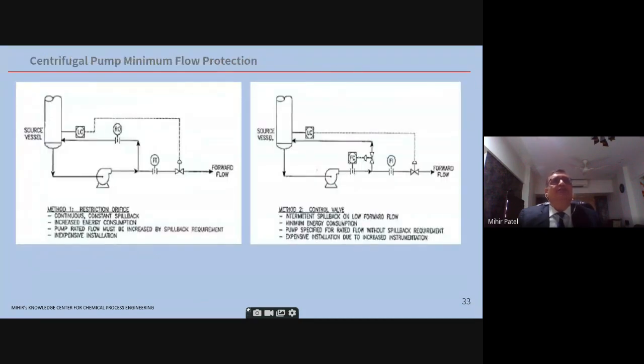Now we come to centrifugal pump minimum flow protection. For a centrifugal pump, to avoid cavitation, there is a minimum safe flow, MCF what is called. It has to be ensured that the flow is always above that. There are two ways you can do it. One is you can have a restriction orifice going back, as you can see in the left-hand figure. The important thing to remember here is that the flow through the RO has to be added to the capacity of the pump. So if you have a 5 meter cube requirement in the process and the minimum flow through the RO is 1 meter cube, the capacity of the pump becomes 6 meter cube.